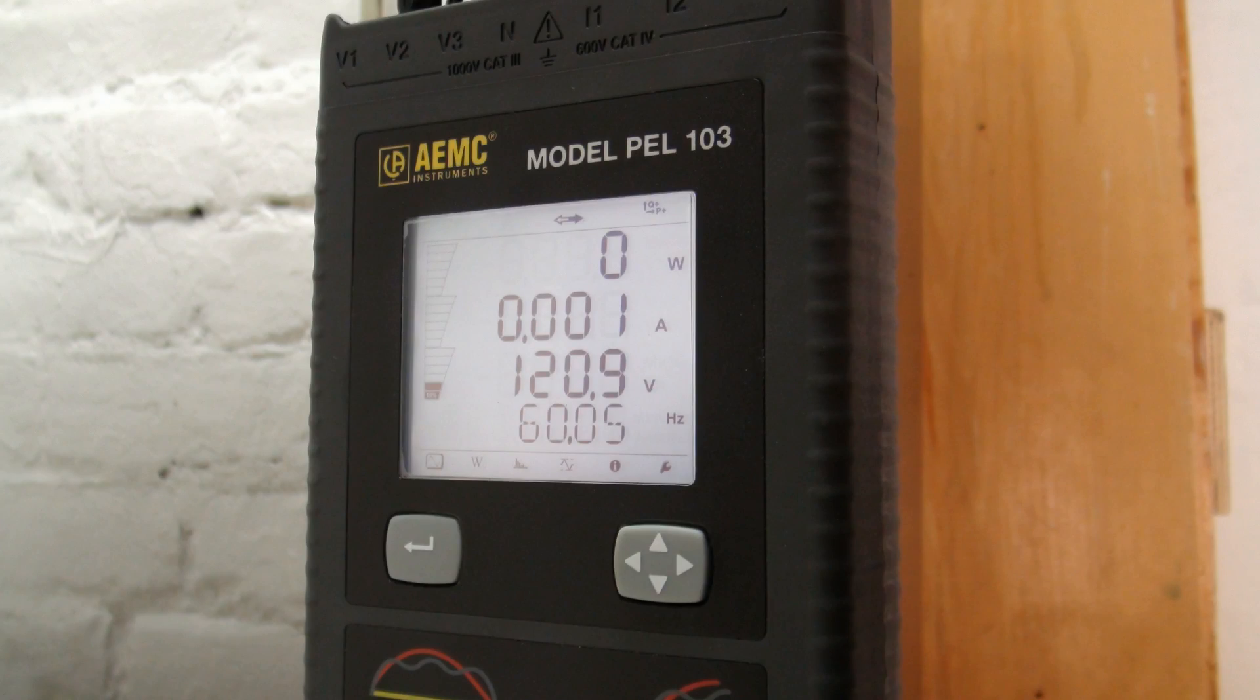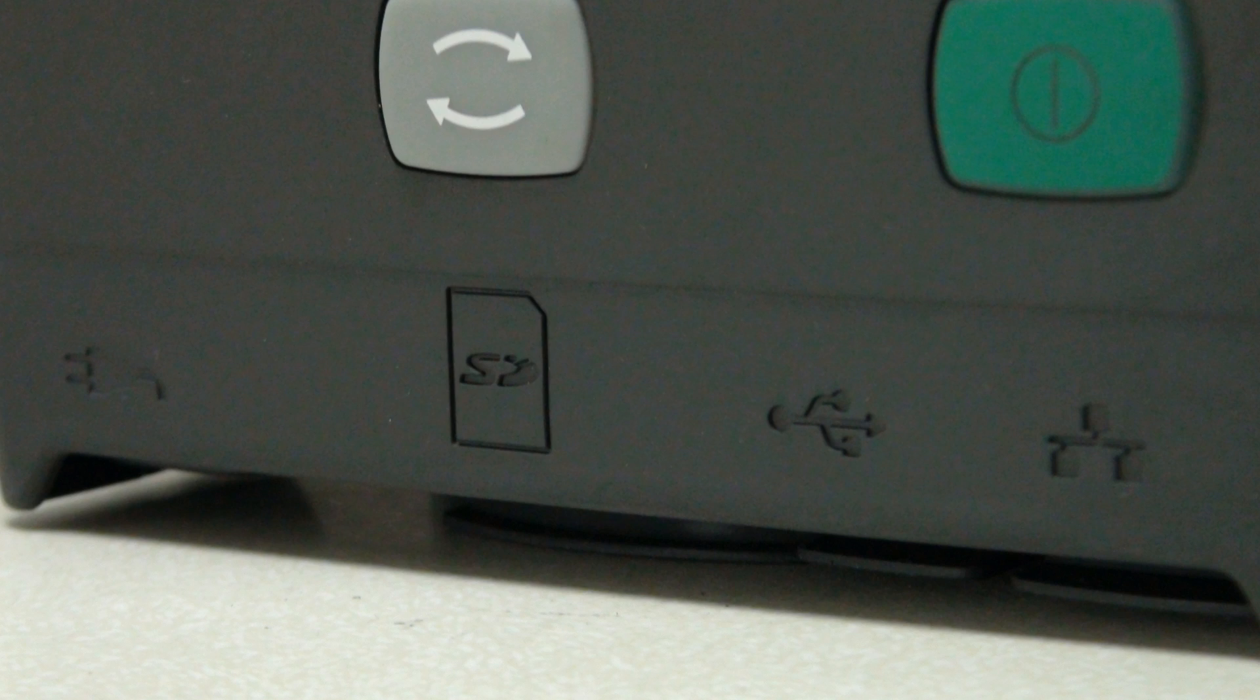It calculates the cosine of theta, so we do know the offset for inductive loads. And also, that's important for when you're doing displacement power factor. It can do regular power factor. It can do total harmonic distortion, again, out to the 50th harmonic.